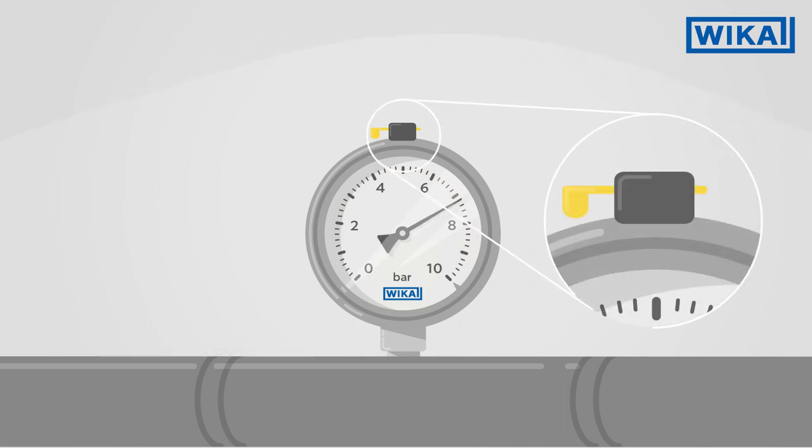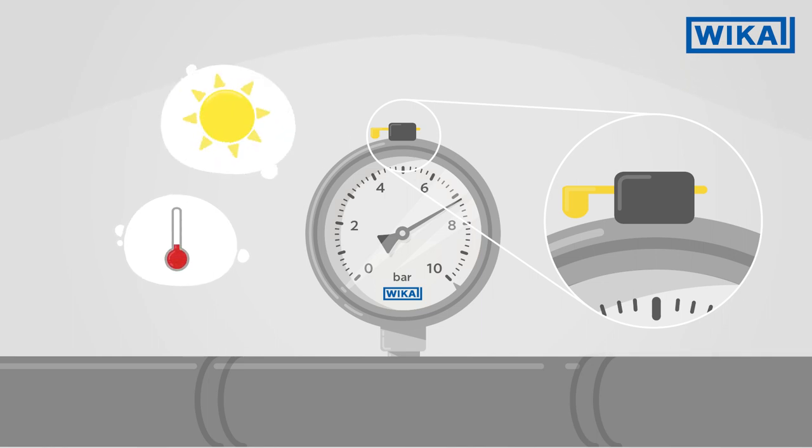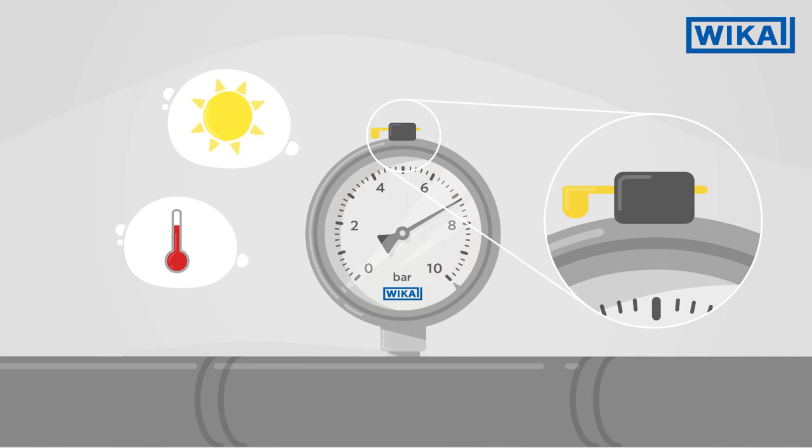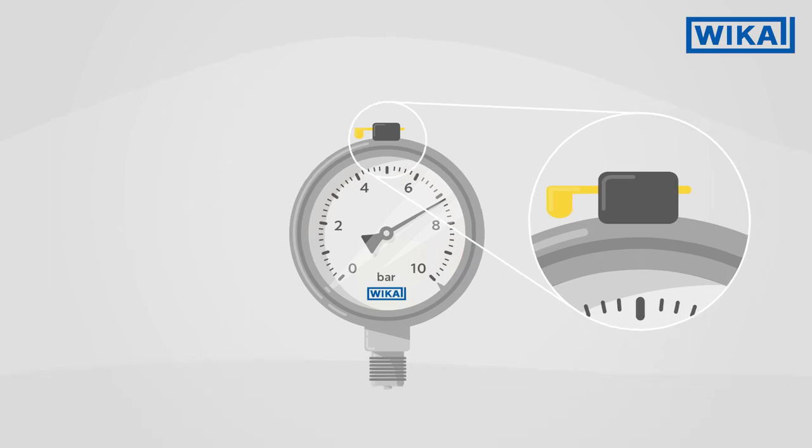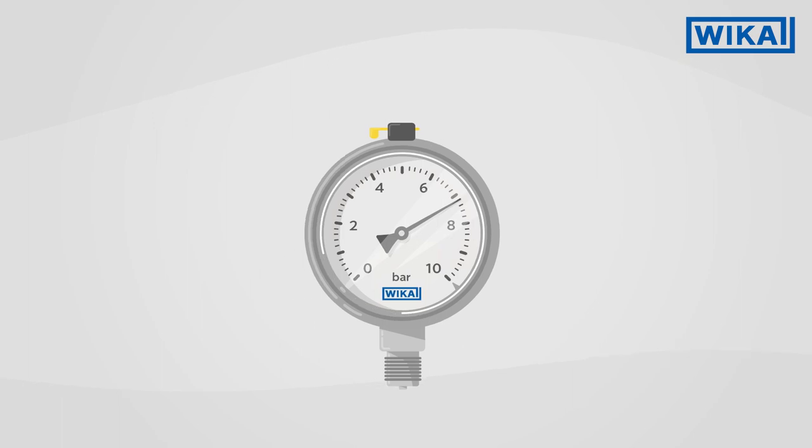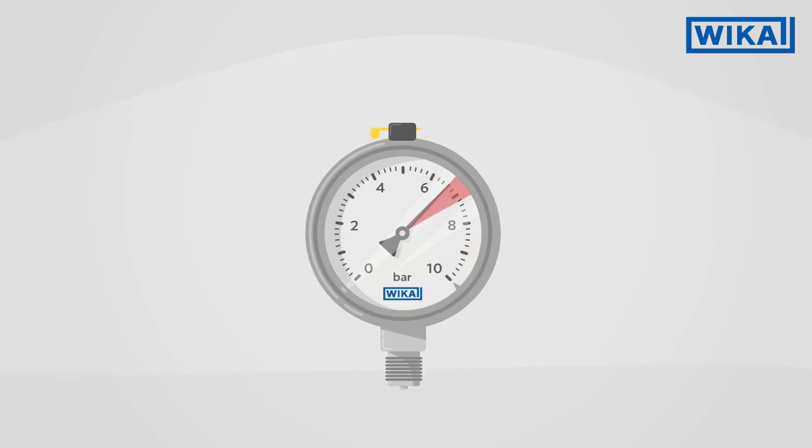With a hermetically sealed pressure gauge, temperature fluctuations, for example with direct sunlight, can mean that the internal pressure in the case is altered. This pressure change in the case has an effect on the measuring system and distorts the displayed measuring result.